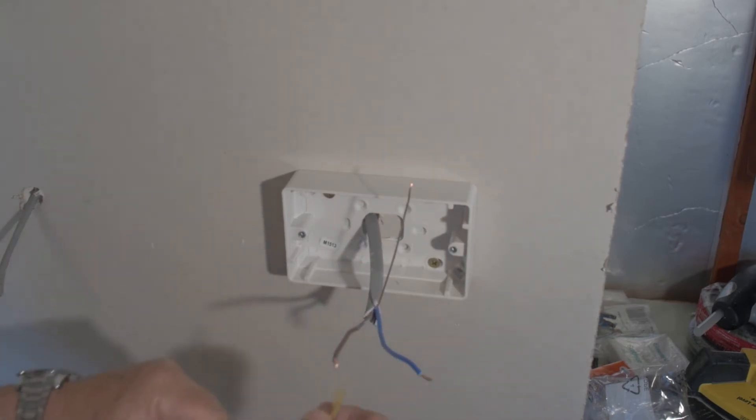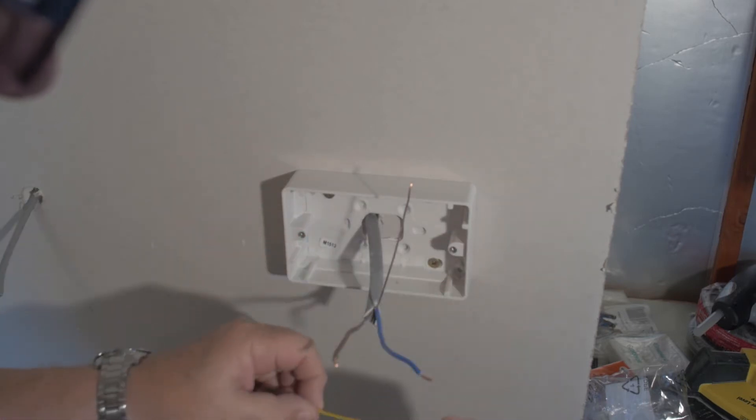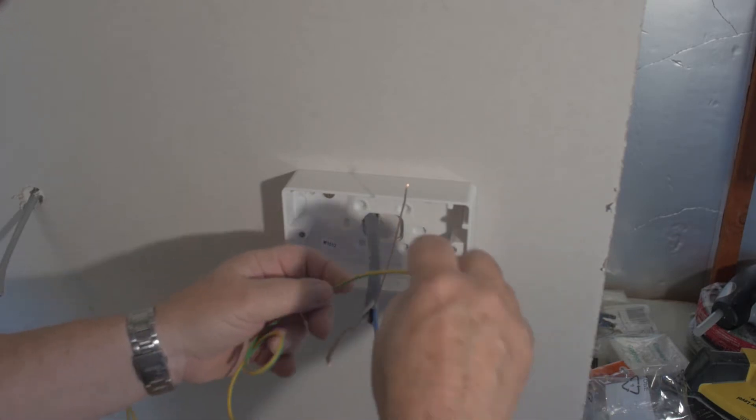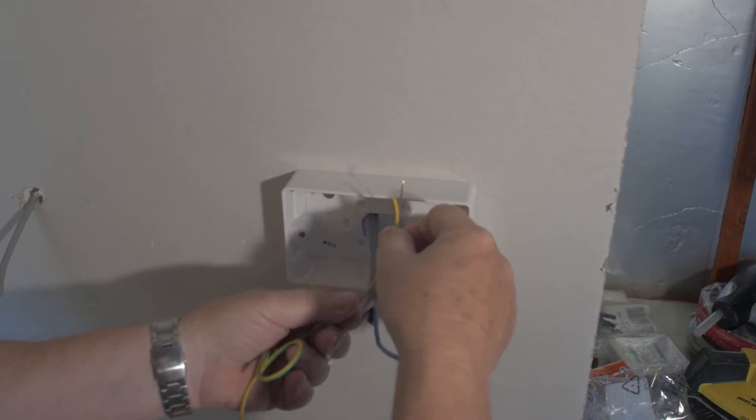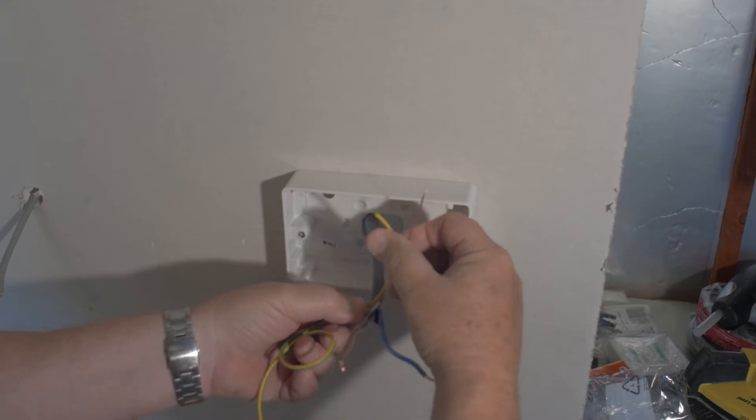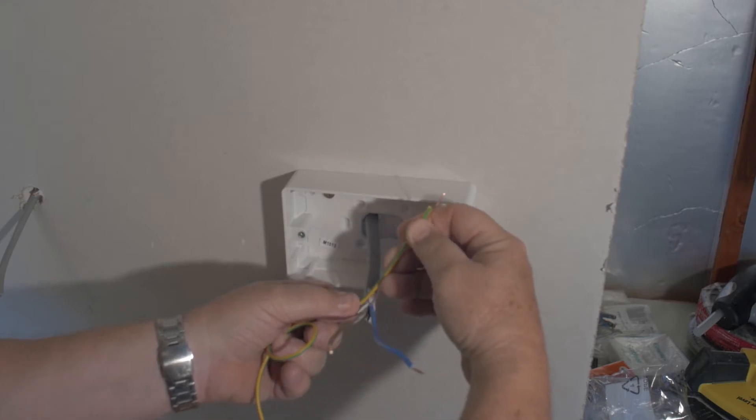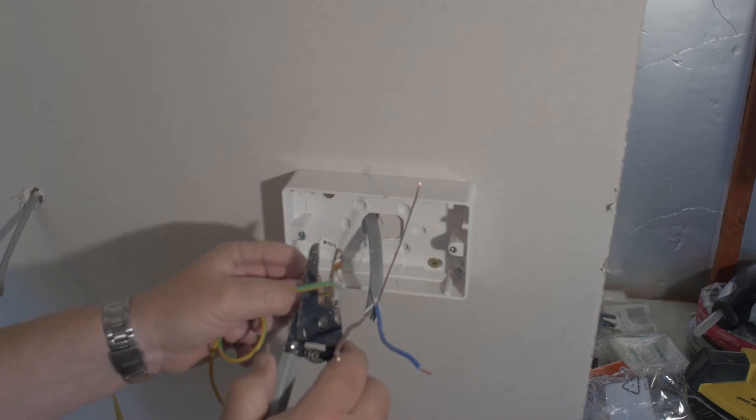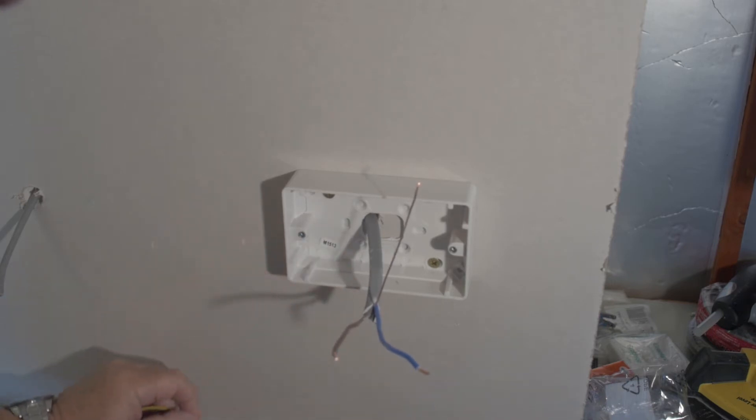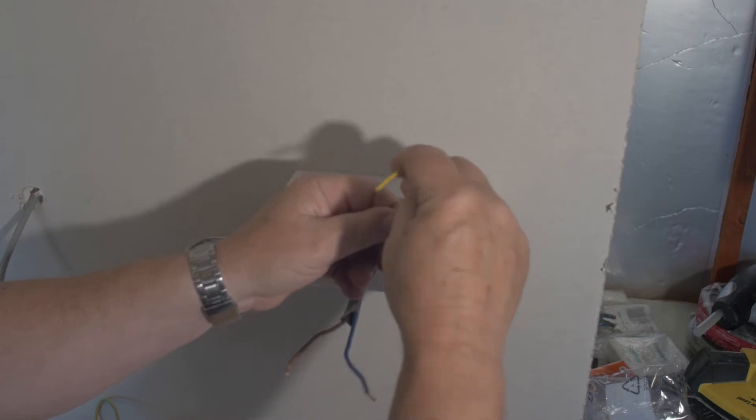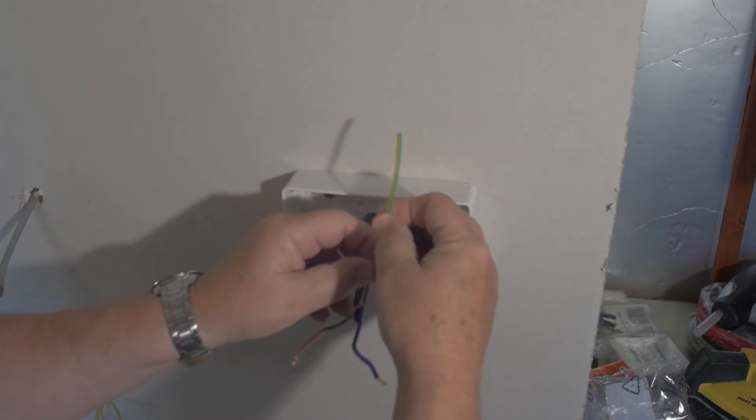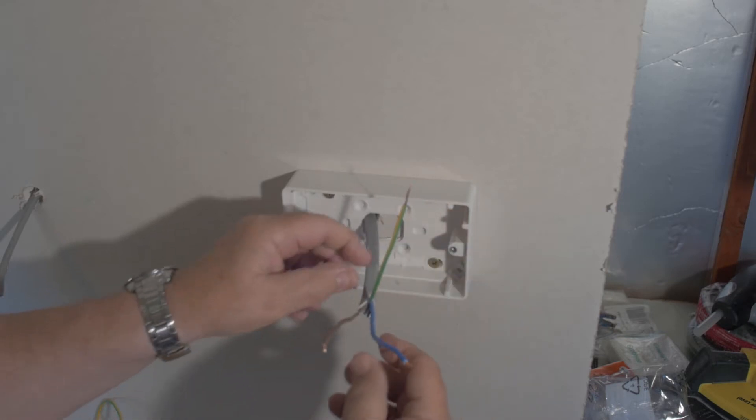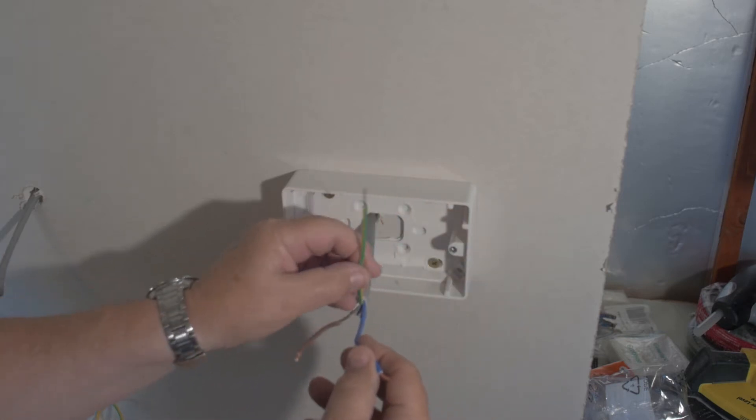And then we need to take some cabling. This is green and yellow. This is a sleeve for the earth cable. Now you can see it's always there, always the same color. So just hold it up so that you've got the same distance as the earth and the live cable, and just snip off a piece and place it over the wire. So you've got a nice protective sleeve there for the earth.